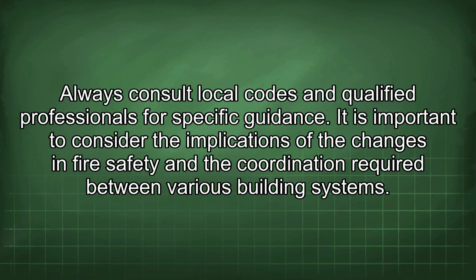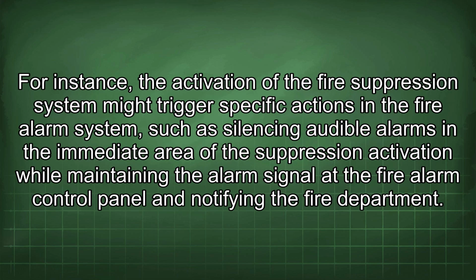Always consult local codes and qualified professionals for specific guidance. It is important to consider the implications of the changes in fire safety and the coordination required between various building systems. For instance, the activation of the fire suppression system might trigger specific actions in the fire alarm system, such as silencing audible alarms in the immediate area of the suppression activation while maintaining the alarm signal at the fire alarm control panel and notifying the fire department.